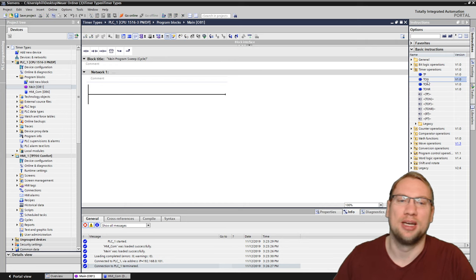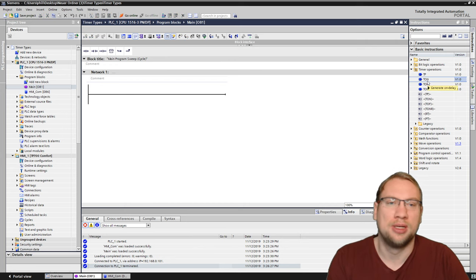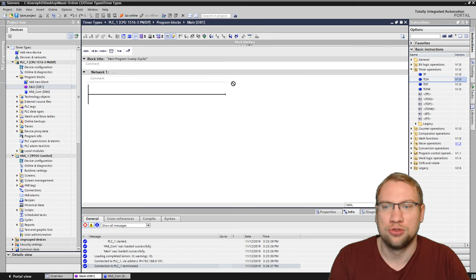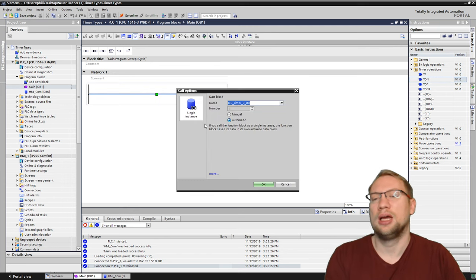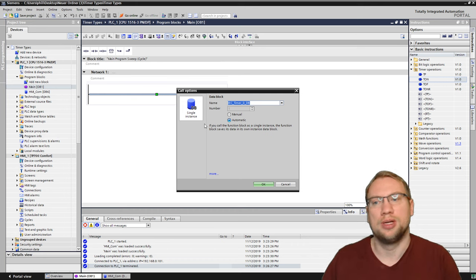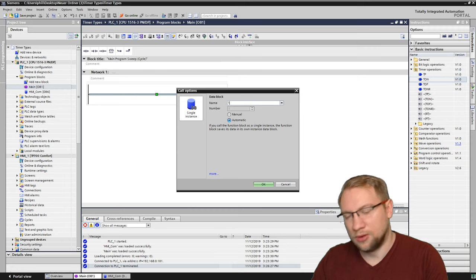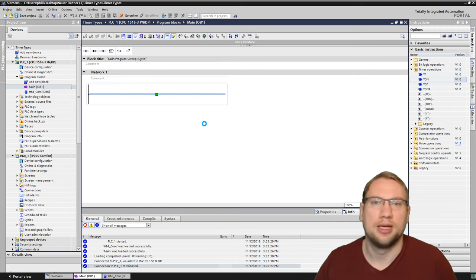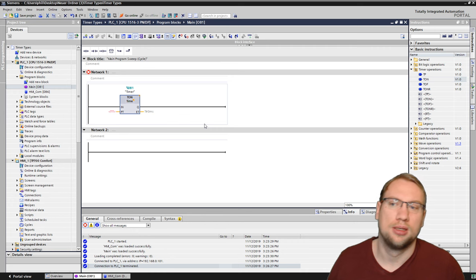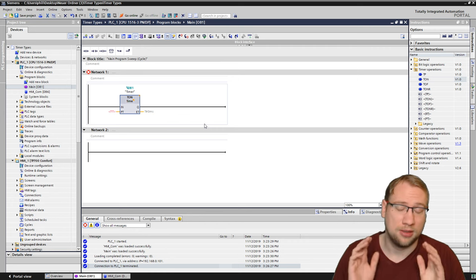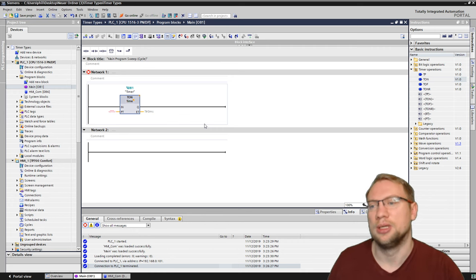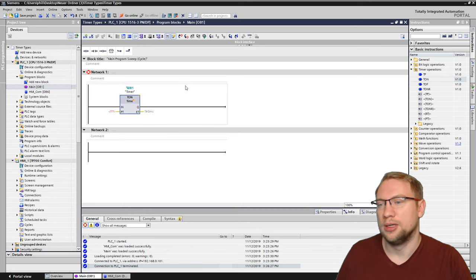Let's take the on-delay timer. You can just drag and drop the on-delay timer into your program. You see the green dot, it's here. And the program TIA is going to ask me, do you want to create an instance? Yes, I want to. And this I want to call, this is my timer. You can give it any name as long as it's unique. This name must not be there in your program two times. It has to be unique.